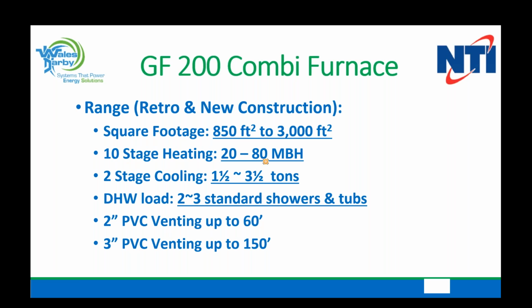You also have the ability in cooling to have 2 different stages of cooling. And there's preset ranges on the controller for your 2-stage cooling. That is adjustable. So if you have a 2-stage condenser outside and you want to tie it directly into this unit, you have the ability to do that, and you can match the CFM for the stages of the outdoor unit. So from a domestic hot water standpoint, again, it's a Navien tankless water heater. We can handle between 2 and 3 standard bathrooms with tubs. Venting, 2-inch PVC up to 60 feet, 3-inch PVC up to 150 feet.